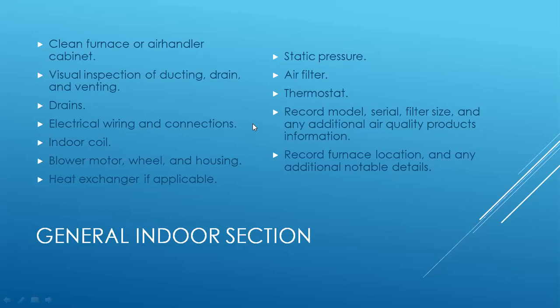Check all your electrical wiring and your connections. By that I mean visually inspect the wiring, you know, hand check the connections. If you see something that looks damaged or burnt, what have you, that's something you want to address. And I'll do that for basically all the wiring: thermostat wiring, low voltage, motor wires.